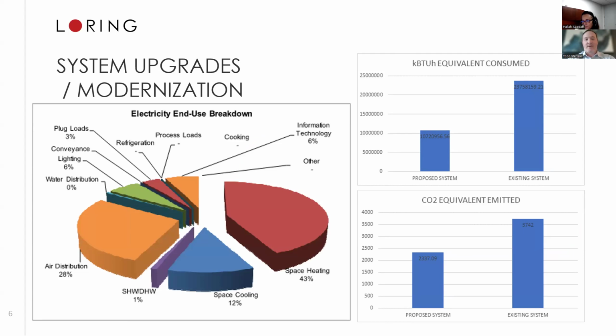One thing we're doing is breaking out, like I said, the energy use to the energy being consumed to its end uses. This is a pie chart that would come out of an energy model following an ASHRAE level 2 or 3 energy audit. And these are useful so we can see what parts of the building are best to be attacked for energy reduction purposes. So in this example, the space heating and air distribution and cooling are most of this building's energy use. So those are the 3 areas where we would start looking at in order to have an idea of where we're going to attack to reduce energy with our energy conservation measures.